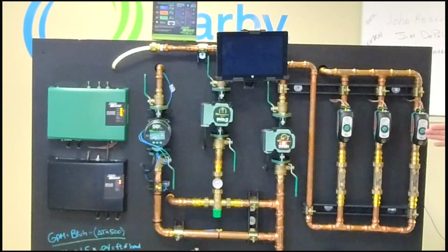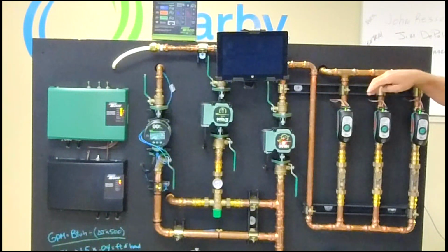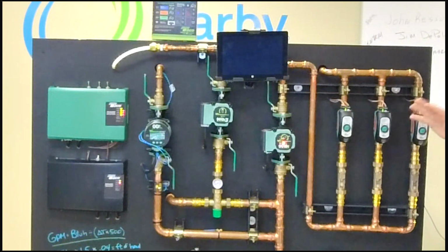So everybody here is opening up, and we only pull power to open up. Right now they're open and they're not pulling power anymore, because inside the head is a circuit board, and on that circuit board is a capacitor that stores power. I don't know if you were able to see it, but as we first turned these on, we could call this a cold start. This would be the first call of the season. They did flash for about, I'd say, 20 seconds, and that was charging up the capacitor. Once the capacitors were charged up, the valves opened. The next call for heat, they will open up right away.